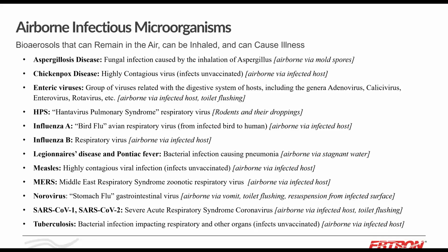Betsy, Gene Hackman's wife, passed away from HPS. They had rodents in the house. It's not known whether it's through direct contact or through the air, but these things are possible. So it's very important to make sure that the space is well maintained, that you don't have moisture. ASHRAE has recently set requirements for moisture at a 59 degree dew point as a max or 60% RH.